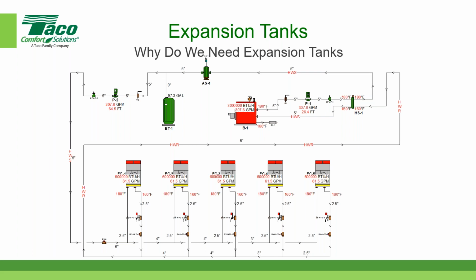To be quite honest, once you get above a certain size, I would go with a full acceptance tank—that's me talking. The price difference isn't that much, but there's a little more safety, fewer installation issues, pre-charge considerations, and so on. Maybe it's oversized a little, but if you're in a bind for a replacement or schedule, or have a hot job, call around—any one of these can work.